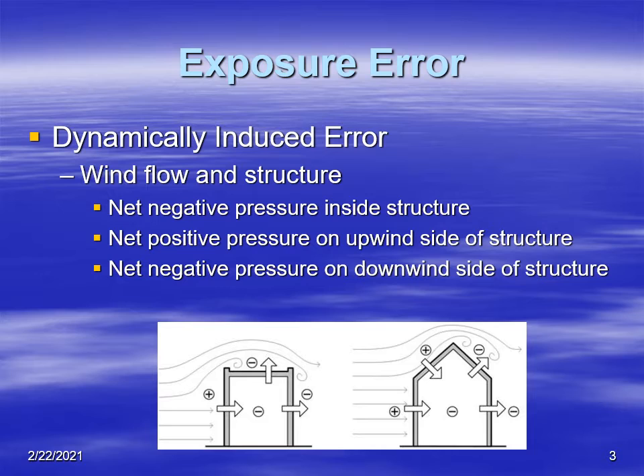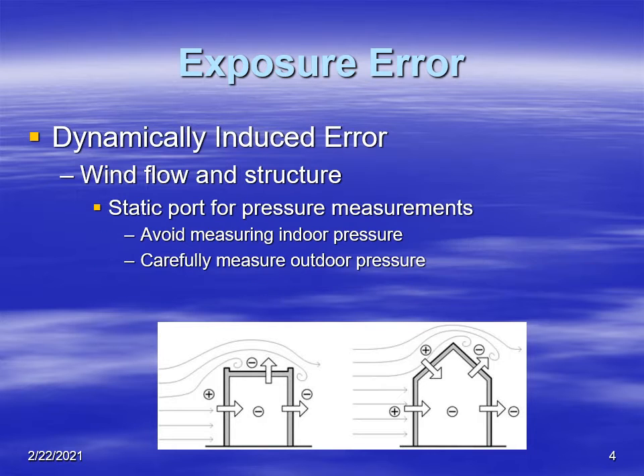So it's important when you're measuring pressure to make sure that you have good coupling between the barometer and the atmosphere. One method to avoid pressure errors — in other words, measuring the structure pressure or the dynamic pressure instead of atmospheric pressure — is to have a pressure line, a static line that goes from your pressure transducer, the barometer, to the outside air so that it can measure atmospheric pressure.